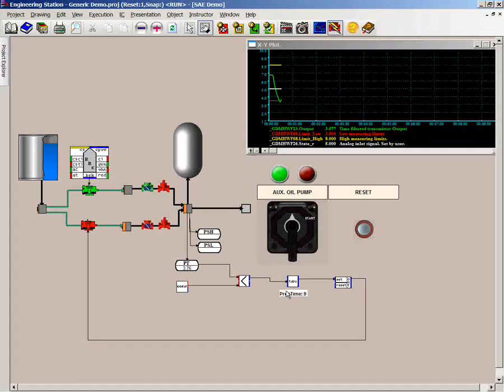As we have seen, the standby pump auto-started correctly, but not in time to prevent a trip, represented by the red line on the trend and audible alarm. Now we will test possible changes in the design and how they will impact and possibly improve the design. But first, we'll restart the first pump.